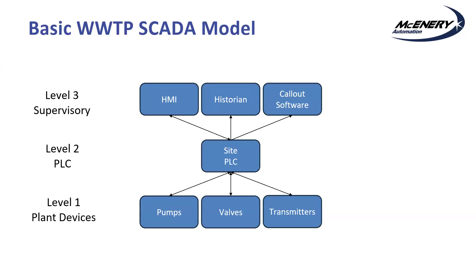So the importance of SCADA for a wastewater system is that the HMI system will allow operators to have all of the data back at one spot, so you can get more informed and quicker responses, either based on operator interaction, or we can go as far as using the controller to have automated solutions for key situations that happen in the plant.